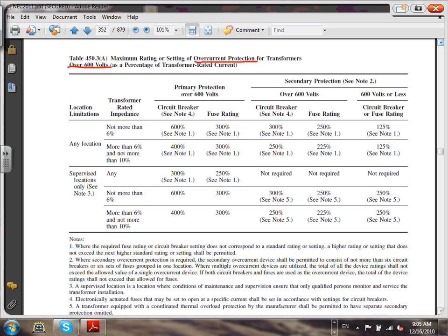So here's the primary. I can't emphasize this one. This table, you use it if the primary or the secondary are over 600 volt, or both. All right, any location. Unless you hear otherwise, you're always going to be in any location, and you default to an impedance of 6%, always, unless you know otherwise. And primary protection over 600: if your voltage is over 600, like 13.8 kV, that's a good example, then on the primary, unless they tell you otherwise, you're always fusing.